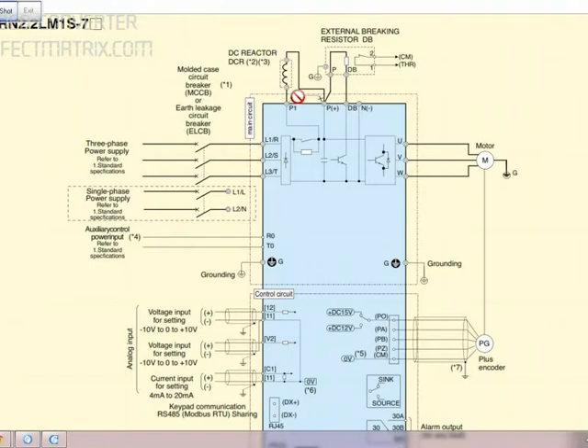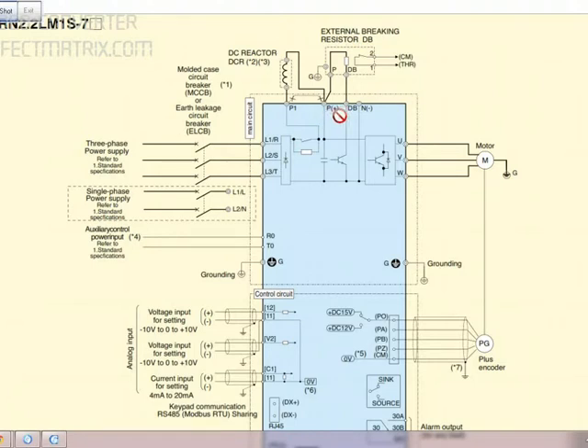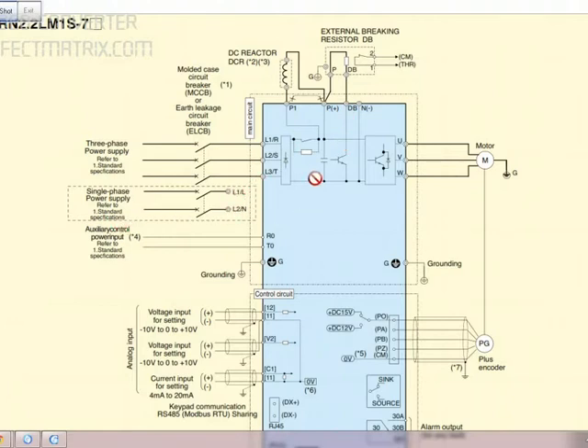Normally we connect P1 and P plus to the DC reactor here. This is one part of it. And other thing is we can connect an external braking resistance, that is between P plus and DB. So if you have a single phase, then you can connect to L1 and L2.